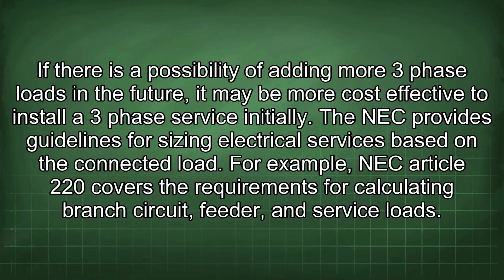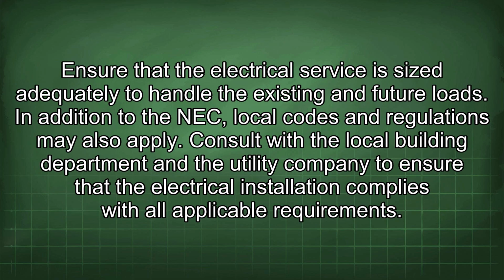If there is a possibility of adding more 3-phase loads in the future, it may be more cost-effective to install a 3-phase service initially. The NEC provides guidelines for sizing electrical services based on the connected load. For example, NEC Article 220 covers the requirements for calculating branch circuit, feeder, and service loads. Ensure that the electrical service is sized adequately to handle the existing and future loads. In addition to the NEC, local codes and regulations may also apply.